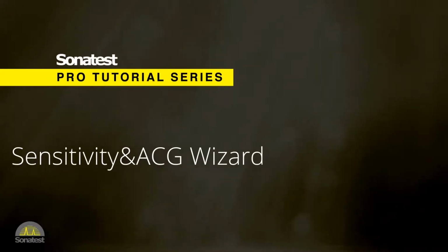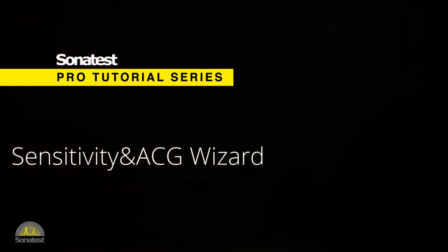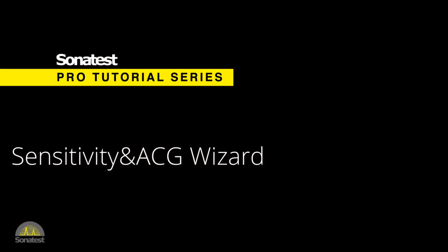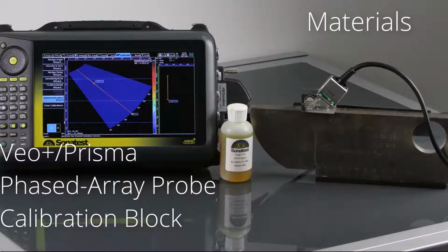Hello everybody. Today's tutorial shows how to set the sensitivity calibration. This calibration should be realised after the velocity and the wedge delay calibration, but before the ACG calibration is performed. The purpose of this calibration is to level the signal response of the reflector for all the angles at the same reference level. To achieve this calibration, you are going to need a Veo+ or Prisma instrument, a phased array probe and a reference block.